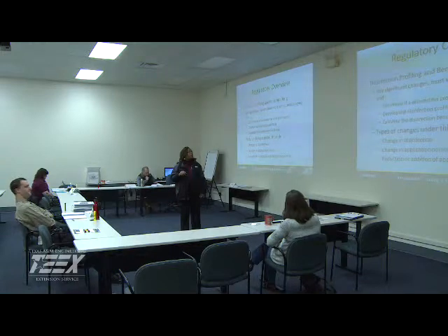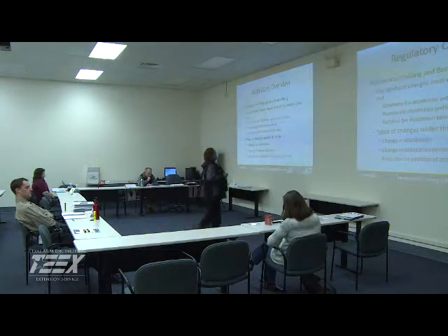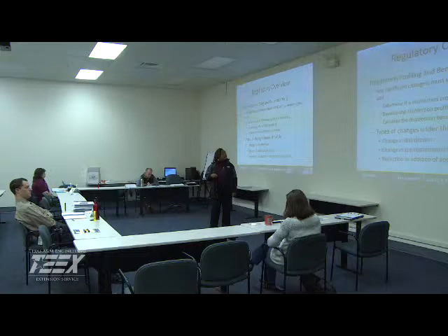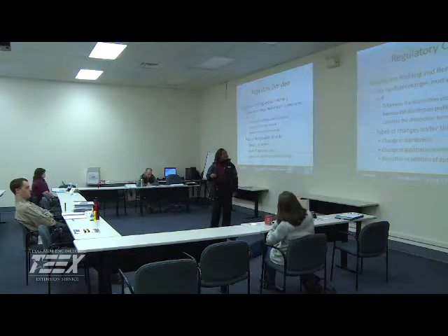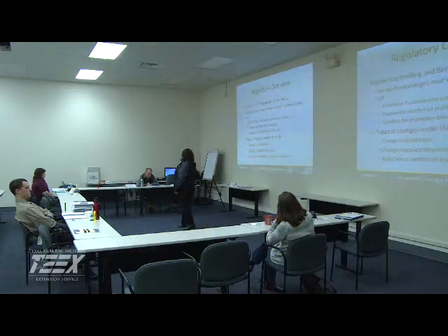So, as far as disinfection profiling and benchmarking, for any significant changes, you've got to work with the primacy agency to determine whether or not you need to do this. They will help you develop the disinfection profile and calculate the disinfection benchmark. Some of the types of changes under this rule are if you want to change your disinfection, or change your application points where you're administering it, or the reduction or addition of your application points.